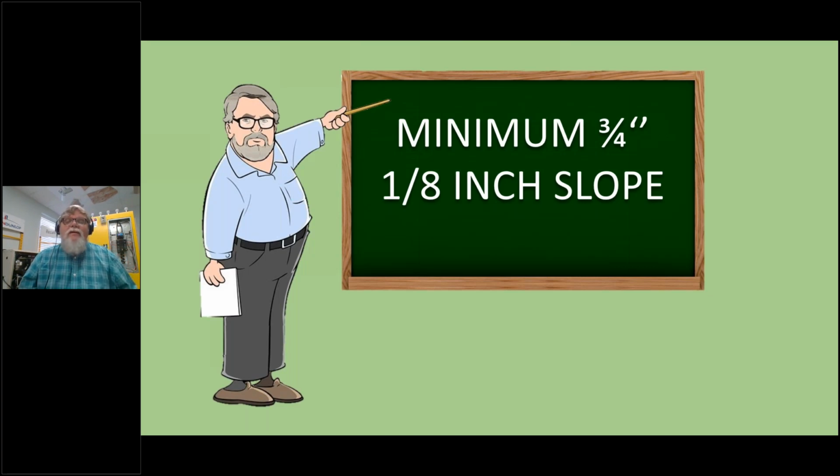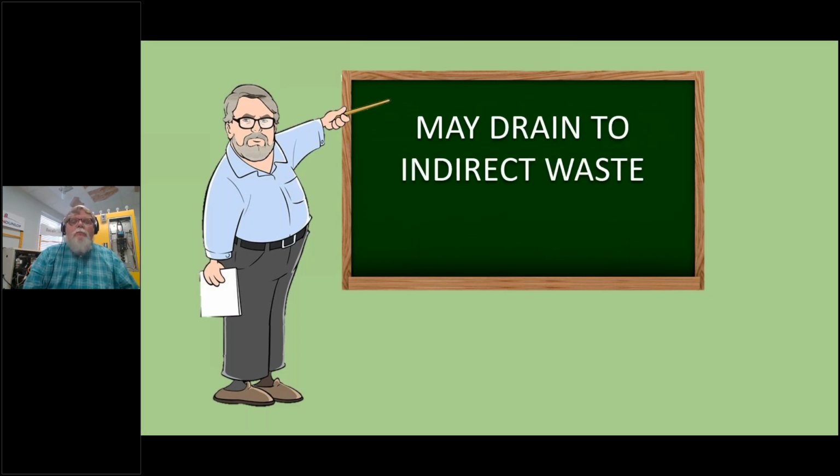The pipe, pretty much across the board, manufacturers and the code say 3/4 of an inch minimum, about 1/8 of an inch slope, supported well. You've got to do that, otherwise the little dips that you get in the pipe end up being a trap. That's what I'm trying to say. So that stuff can slime up pretty bad. So good support, 1/8 inch slope, or maybe a little better if you can, and 3/4 inch, you'll probably do pretty good.